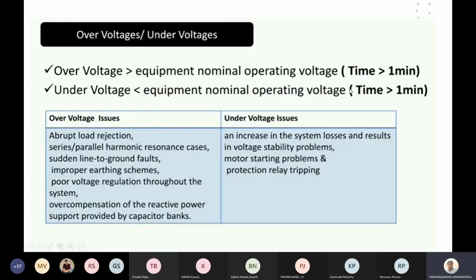If it should occur for at least more than 1 minute of time. So for a single phase consumer, we are expecting 230 volts. So the rated voltage is 230. If it falls below 230, say 180 or 200, and it lasts more than 1 minute, it is said to be under voltage. Whereas we are expecting 230 volts of supply only. So 250 or 270, if it occurs for 1 minute or more than 1 minute, is said to be over voltage.